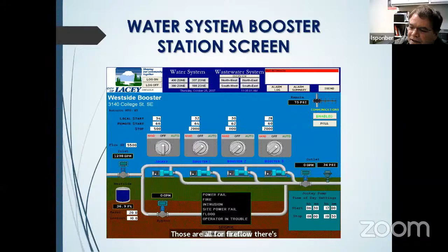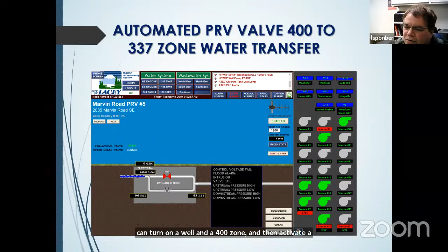We also have automated PRV valves. Our system is pretty complex. We have like 9 pressure zones. So we have several places throughout the city where we can move water down the pressure zones. So these PRVs are automated and they actually can function like a pump. They can take water from the 400 zone, for instance, and move it to the 337 zone if there's a demand for it. And then you can also take wells. We're real heavy on wells in the 400 zone, but you can turn on a well in a 400 zone and then activate a PRV and move that water to a lower zone.